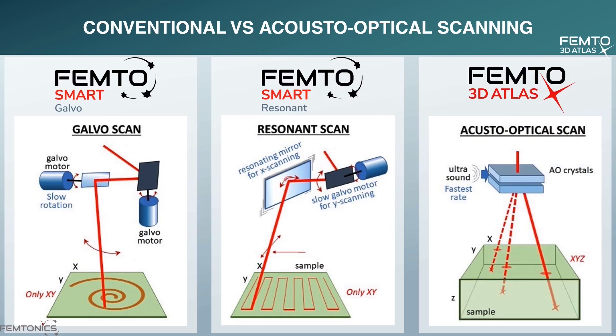Scanning in conventional 2P systems happens with galvo-galvo or galvo-resonant moving mirrors. The inertia of the moving physical parts limits the speed of the system. In the acousto-optical system, you are taking advantage of refractive changes in tellurium dioxide crystals. By eliminating inertia-limited moving parts, you are able to reach a yet unforeseen scanning speed. This does not mean you cannot perform galvo or resonant-like scanning should you wish to, but you also have access to a wide array of new possibilities that lie in random access 3D imaging. That is why we call Femto3D Atlas an all-in-one tool.